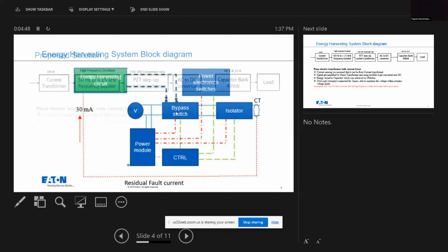As you can see, we have 30 milliamps from the CT, or current transformer. This 30 milliamp signal is given to a high frequency oscillator, which operates from 50 hertz to 15 kilohertz. This range is adjustable; we can use any range.